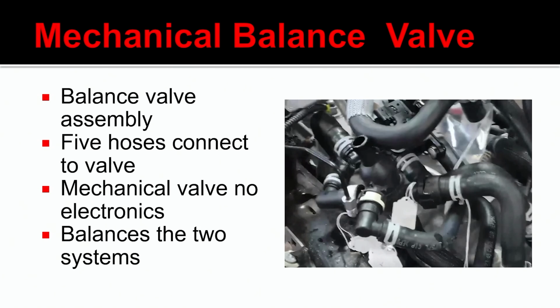Now, there are some valves that are involved. There's a mechanical balance valve. There's 5 hoses connected to the valve, and it's a total mechanical valve, no electronics on it. It balances the flow between the 2 coolant systems in this particular case. So this is a component that could go ahead and wear.